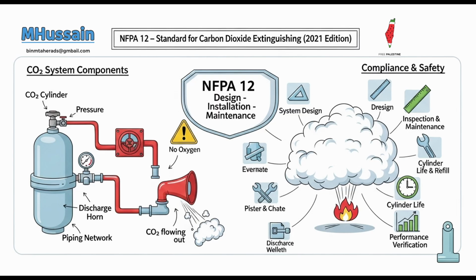Not every fire, as we know, is conveniently contained within a sealed box. What about hazards that are out in the open, like a large manufacturing machine, a dip tank, or a specialized piece of equipment? Right, the non-enclosed hazards. How do CO2 systems handle those? This is where local application systems come into play, and what's fascinating here is how they differ fundamentally from total flooding. How so? Instead of filling an entire space, a local application system consists of a fixed supply of CO2 discharged directly onto the burning material.